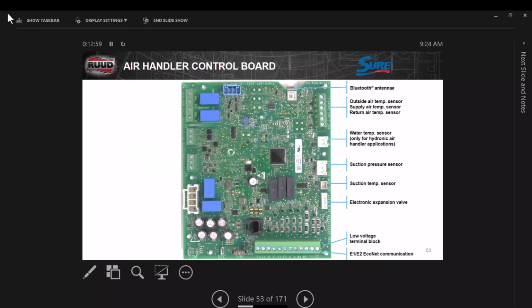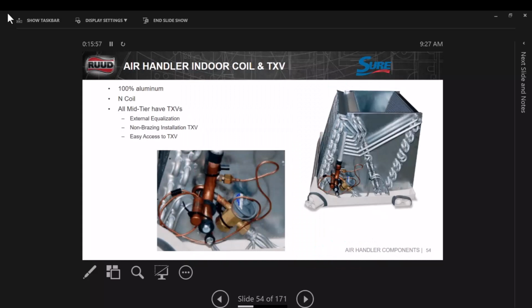We have our outdoor air temperature sensor, supply air sensor, and return air sensors here on the right. We do offer hydronic coils if you have hydronics. We do have an air handler that has that, where you can put your water temperature sensor there. So that's suction pressure sensor, suction temperature sensor, and an electronic expansion valve will plug in right. Low voltage terminal block down here, E1, E2. Just remember, 1, 2 has to be on 1, 2 on all 3 pieces. Evaporator coils, 100% aluminum on the tubes. Mid-tier TXVs are external equalizer, non-brazing, and they're all easily accessible here because everything's up front. Nothing hidden behind all the tubes and everything.